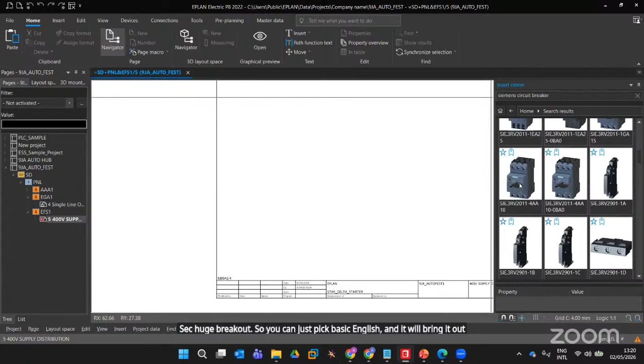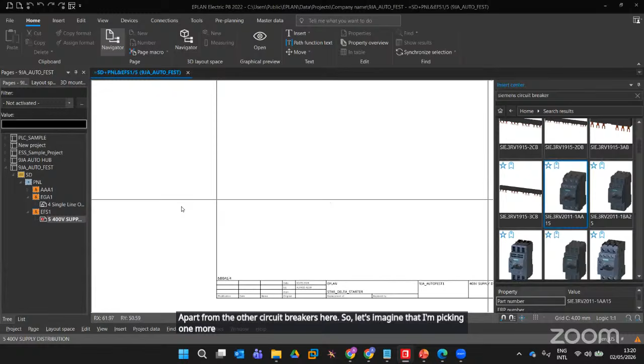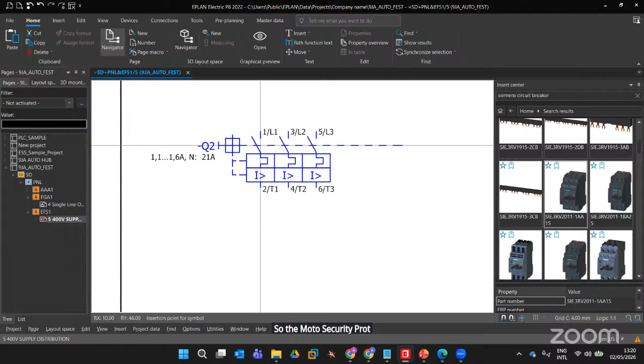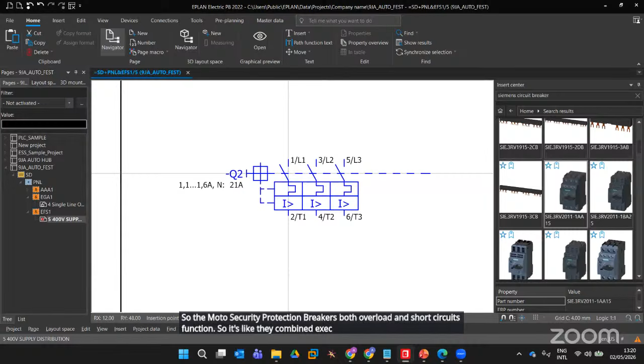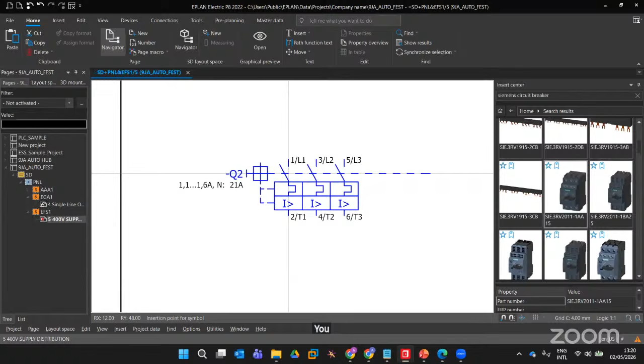These ones are like motor protection circuit breakers, apart from the other circuit breakers we have. So let's imagine I'm picking one motor circuit protection breaker. It has both overload and short circuit function, like they combined a circuit breaker and an overload. If you're using a contactor, you still have to manually attach overload to it, but an MPCB has that feature attached.